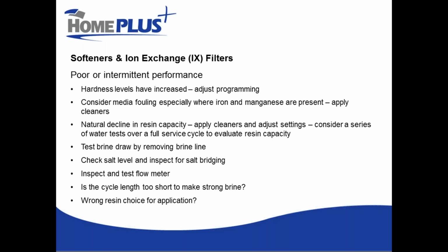So if we disconnect the line from the brine tank and put our water softener or ion exchange filter into the regeneration mode and skip through to the brine draw mode, we should literally be able to feel suction on the end of that line if we put our finger on it. Or grab a glass of water and stick the tube in that glass, and we should literally be able to watch it sucking water out of the glass. If it's not sucking water out of the glass, you have a problem in your control valve. If it is sucking water out of the glass, but you're not getting a good regeneration, you probably have a fault within the components in your brine tank. So it's a really quick way of determining where a problem might be. Very, very handy.